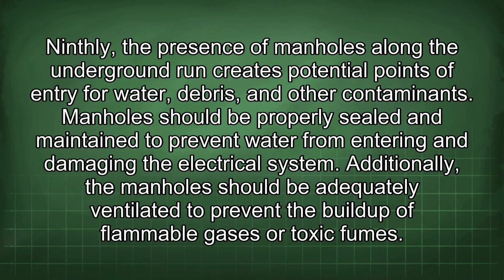Ninthly, the presence of manholes along the underground run creates potential points of entry for water, debris, and other contaminants. Manholes should be properly sealed and maintained to prevent water from entering and damaging the electrical system. Additionally, the manholes should be adequately ventilated to prevent the buildup of flammable gases or toxic fumes.